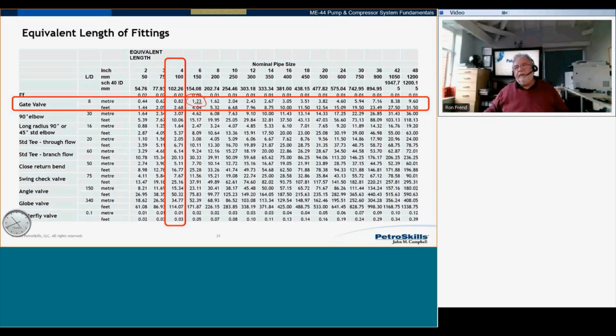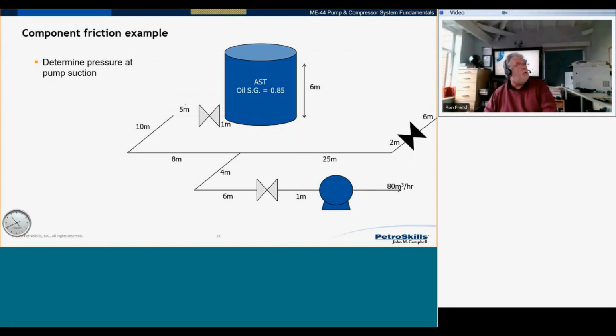So a 4-inch pipe and a 4-inch gate valve is going to give me 0.82 meters. Let's do a quick one. We've got an atmospheric storage tank. It's got oil with an SG 0.85. And what I see is the line to the pump. Well, I've got 1 meter here, a gate valve, 5 meters, and I've got a 10-meter run, then 8 meters to a branching T, then a 4-meter run, then 6 meters to another gate valve, and then another 1 meter into the pump.